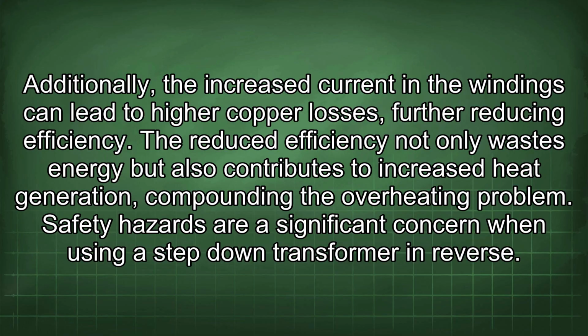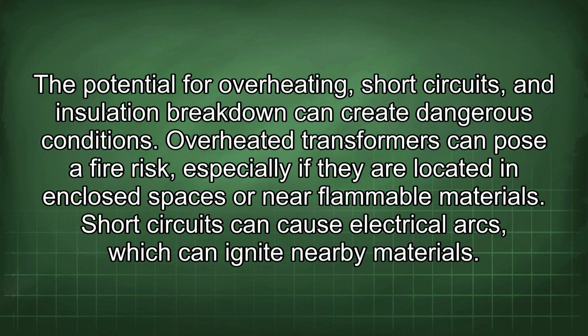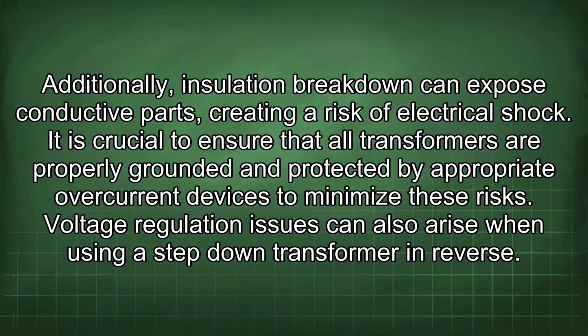Safety hazards are a significant concern when using a step-down transformer in reverse. The potential for overheating, short circuits, and insulation breakdown can create dangerous conditions. Overheated transformers can pose a fire risk, especially if they are located in enclosed spaces or near flammable materials. Short circuits can cause electrical arcs, which can ignite nearby materials. Additionally, insulation breakdown can expose conductive parts, creating a risk of electrical shock.